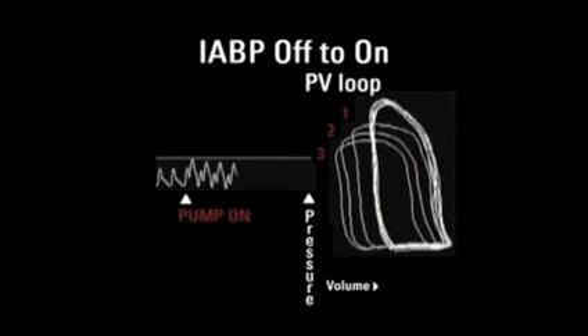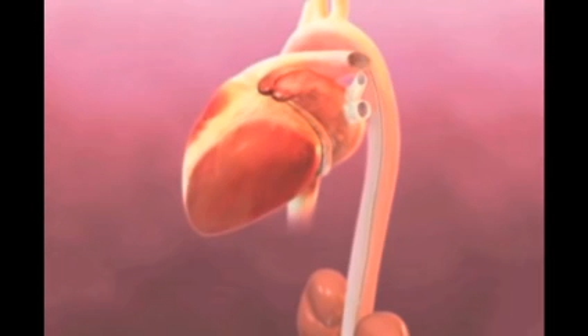Because the pumping action of the heart and that of the intra-aortic balloon pump occur in different phases of the cardiac cycle, this technique is also referred to as balloon counterpulsation. The resistance of flow of a gas in a tube is related to a number of factors given by Poiseuille's law. The narrow bore of the catheter, the length of the catheter, and the viscosity of air make it impossible to inflate and deflate the balloon at the rapid flows required. As a result, the intra-aortic balloon pump uses an alternative gas that is lower in density, thereby reducing its viscosity: helium.